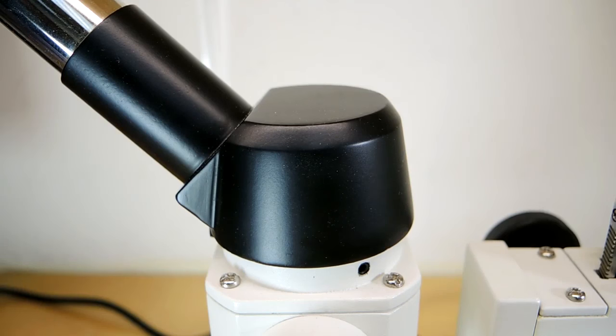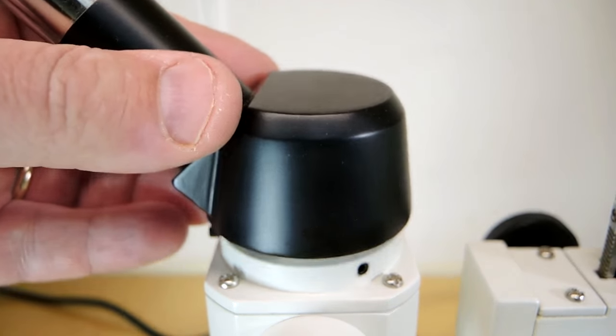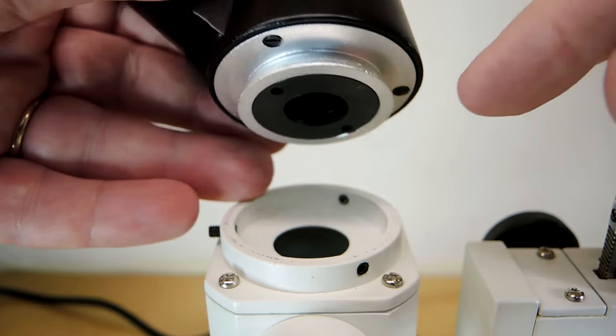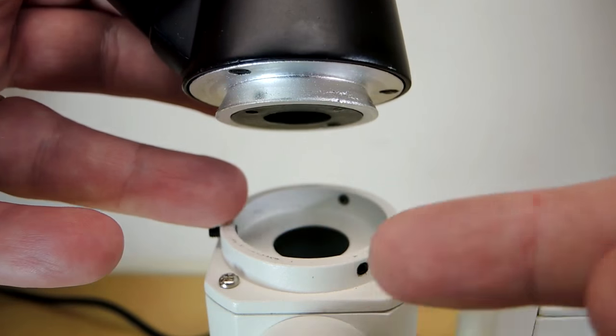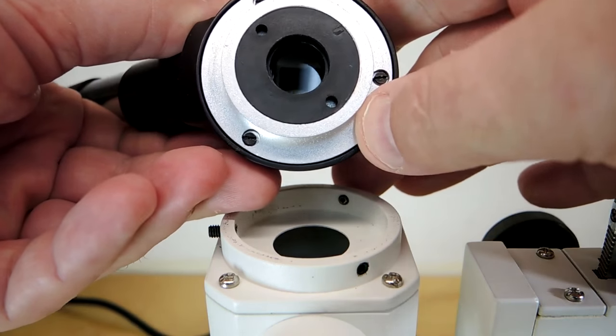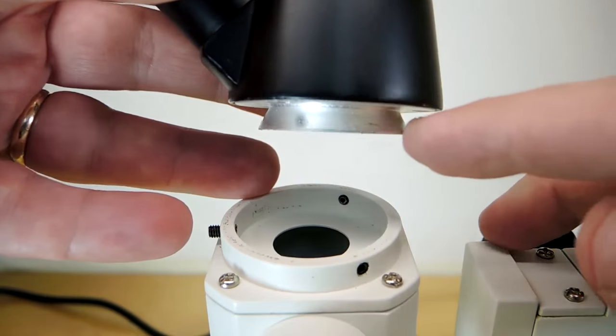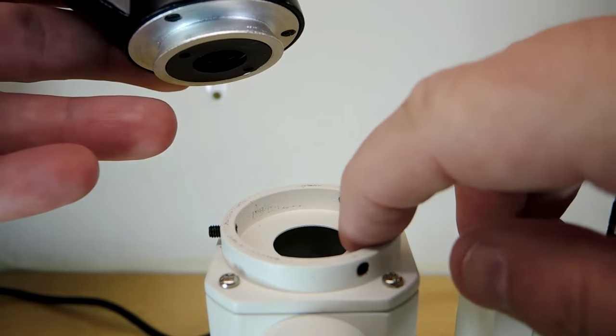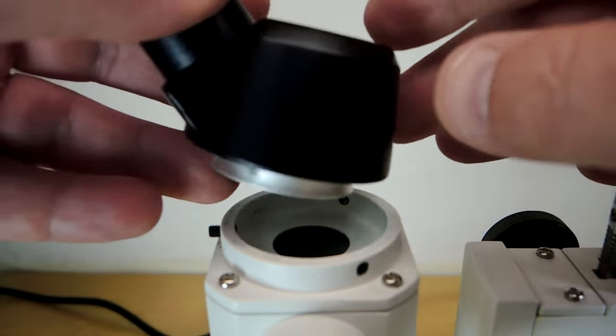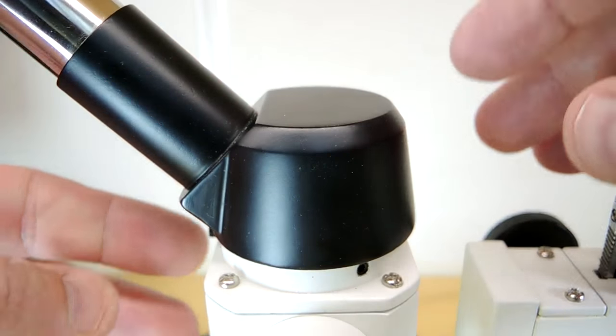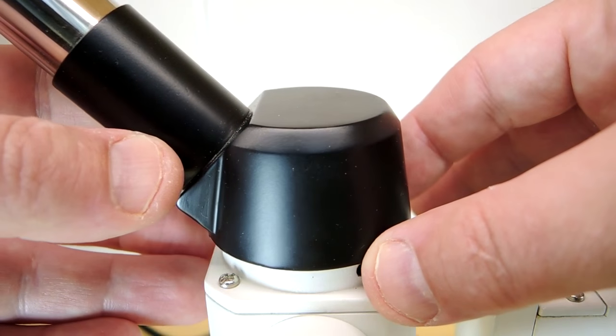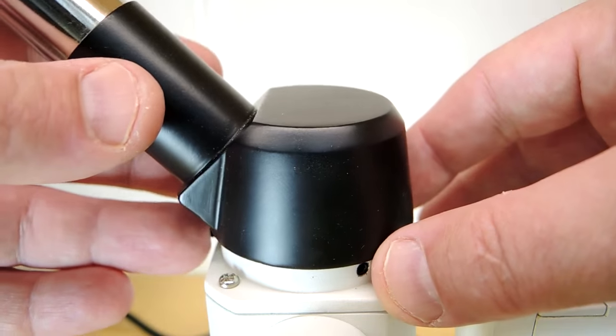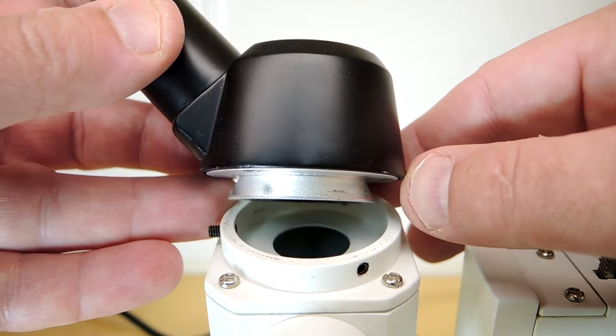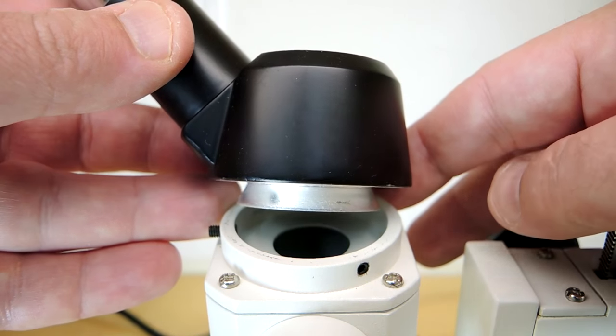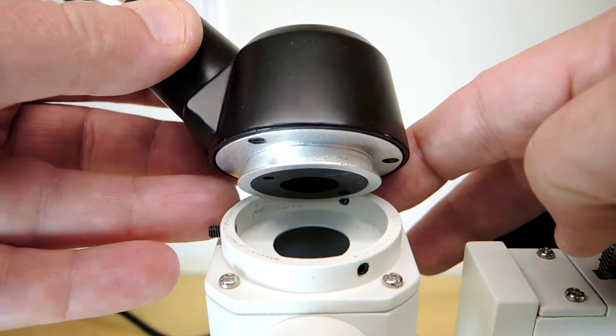There are a number of really interesting construction details in any microscope, and this one's no different. For example, you obviously need the light to always line up through all these various bits of mechanics. You see this sort of dovetail shape here, then a circle here, and there are three set screws. Of course, you put the head down, you can use these to put the head exactly in center, then you tighten down this set screw. It's an extremely effective approach to aligning optics, and obviously dead simple.